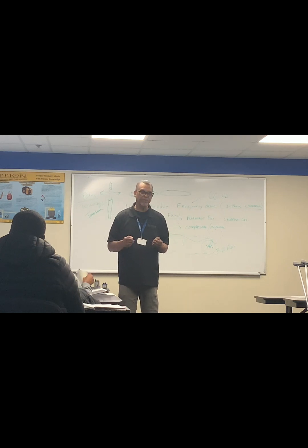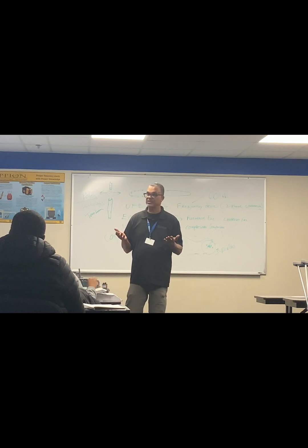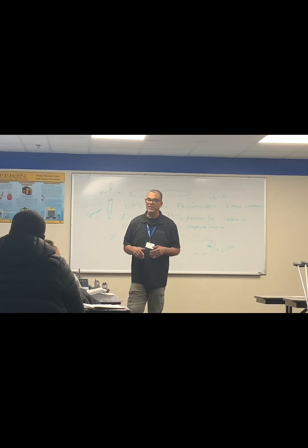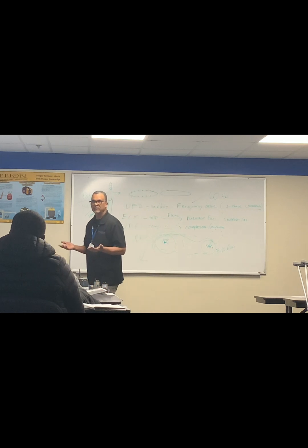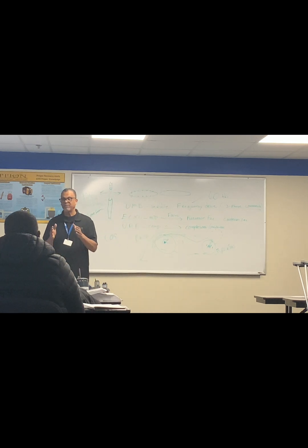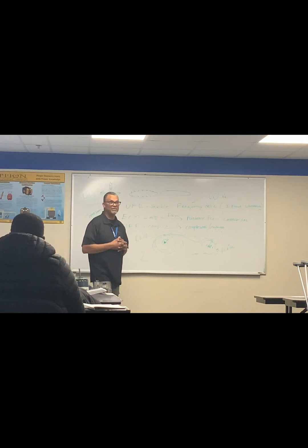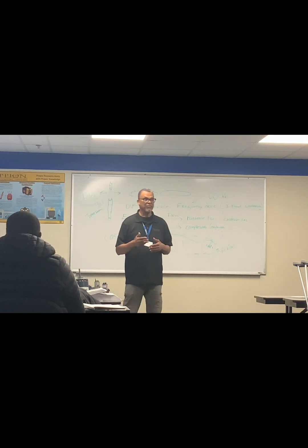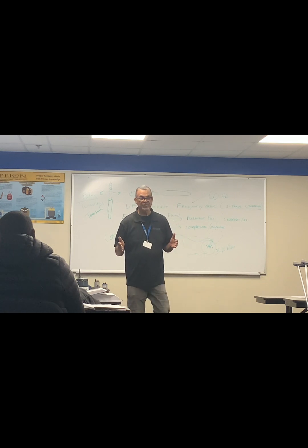And then when we go in the lab, you can look at the nameplate, and it'll tell us on the nameplate what is the design airflow for that furnace. 1825, 1250, 1475, or whatever it is, it's gonna have for that particular furnace, designed with that particular air distribution wheel, with that particular motor. This is the maximum airflow you're gonna get out of it. If you need more airflow, you're gonna have to get a different furnace design.